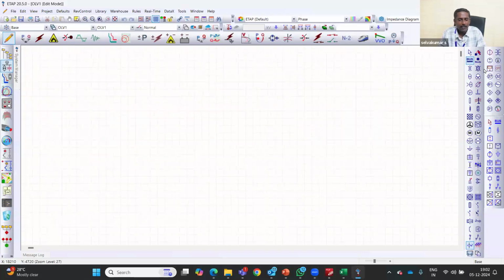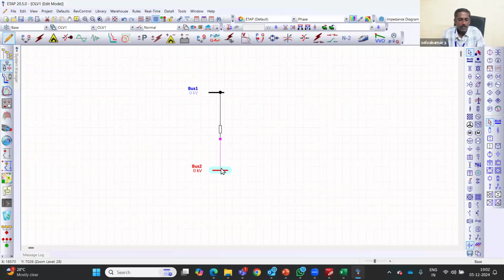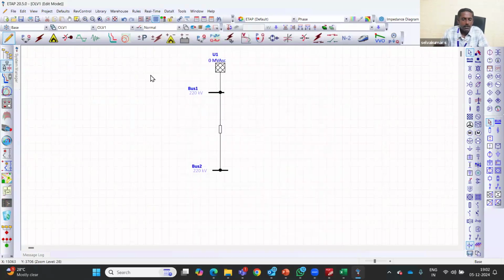Just to give an idea, if you're putting up transmission lines for evacuating power, even a small harmonics injected by the solar inverters can be amplified by the system. So let's take, say, I am expecting a 220 kV transmission line which probably carries 300 megawatt power generated by a solar plant.